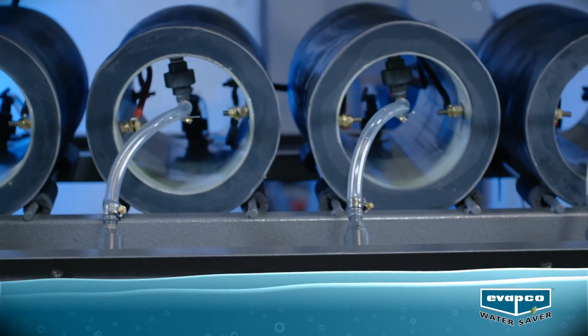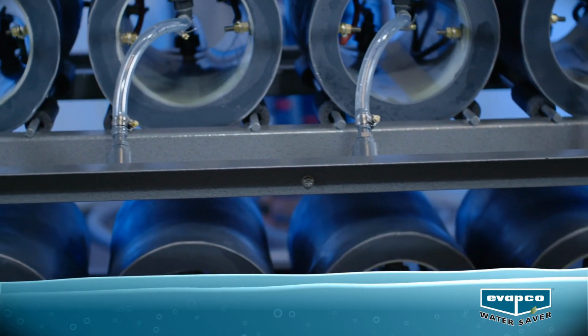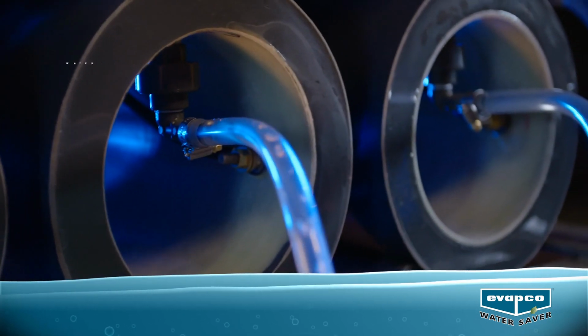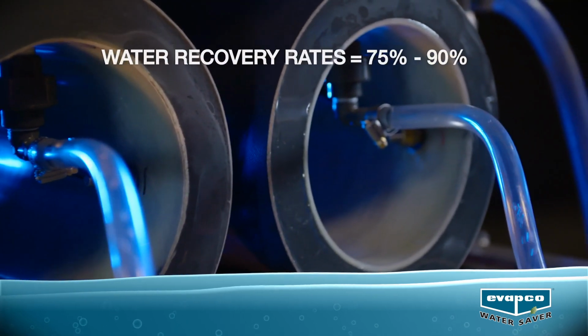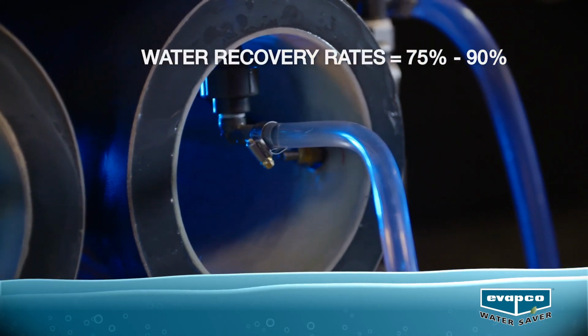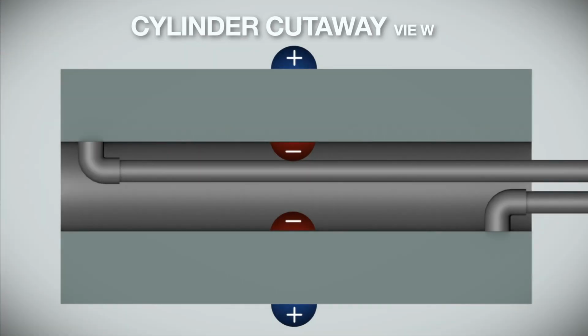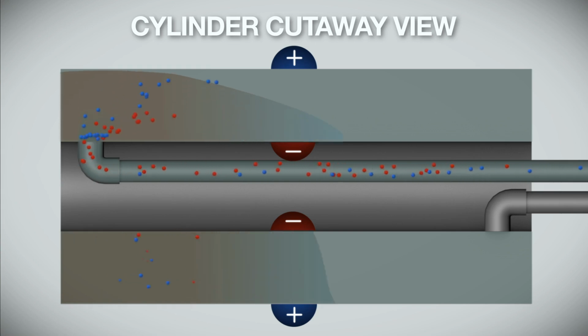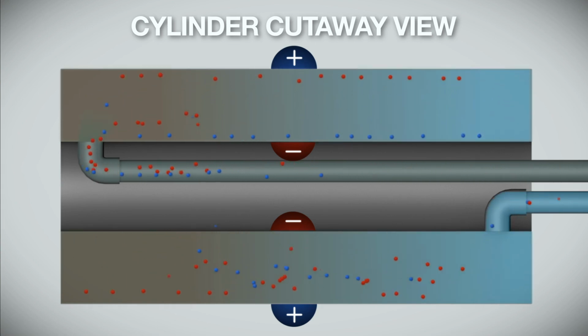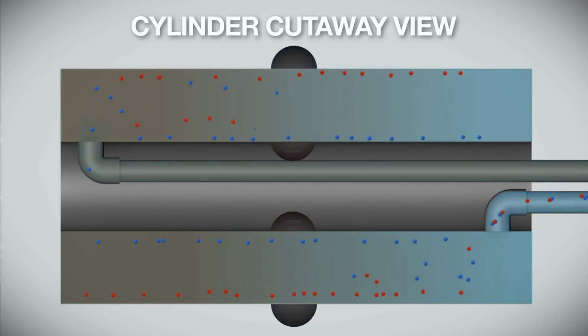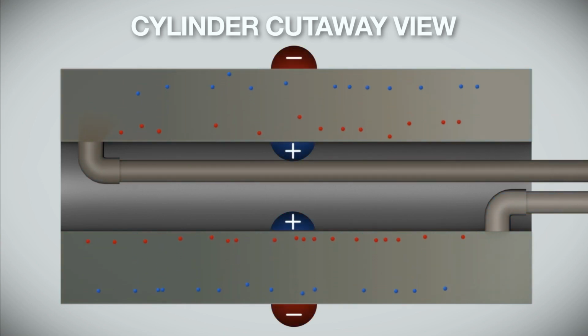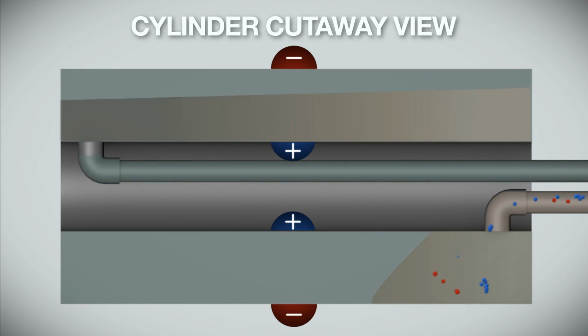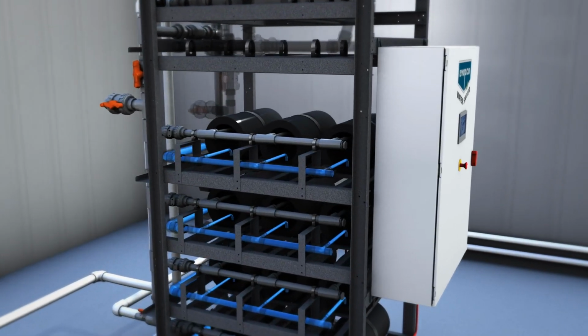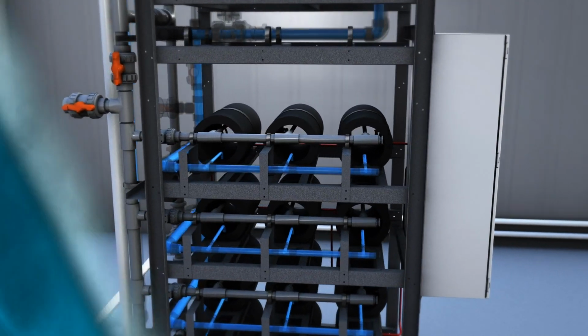The EVAPCO Water Saver provides high recovery rates compared to other ion reduction technologies like reverse osmosis. High recovery, typically 75 to 90%, makes the Water Saver more efficient and economically attractive for evaporative cooling applications. The EWS works by pulling the ions from the water, not the water away from the ions. During the clean water production cycle, a portion of the dissolved ions are captured by the capacitors. Once the capacitors fill with ions, the polarity is reversed and the accumulated ions are flushed to drain. A PLC automatically controls the process. The EVAPCO Water Saver's innovative design saves customers valuable water.